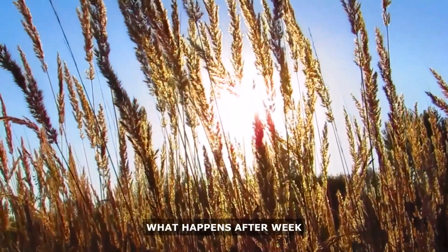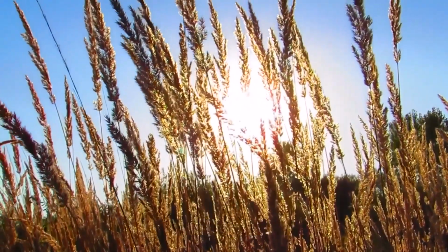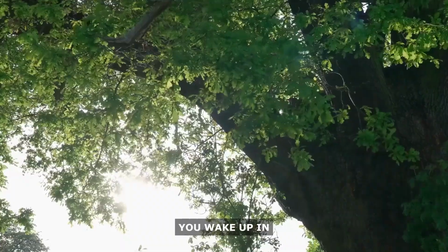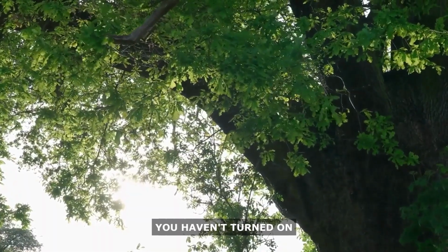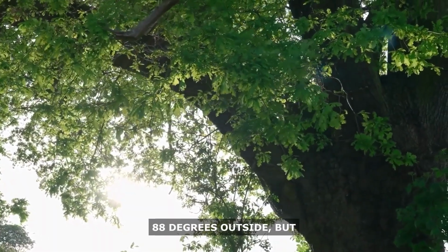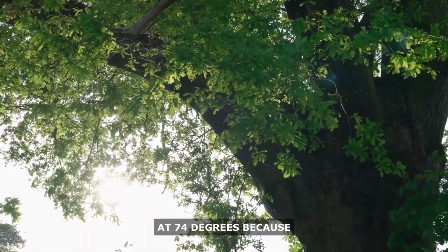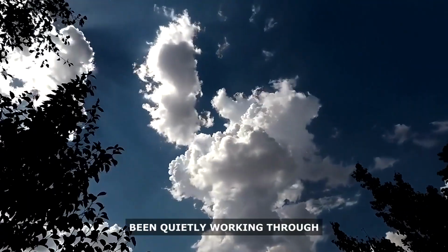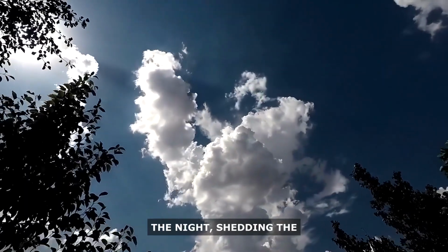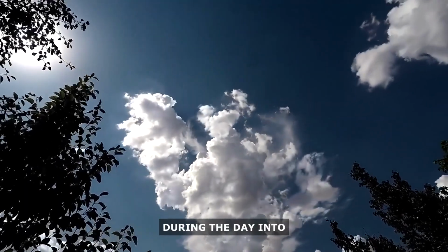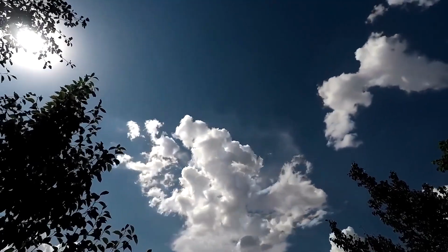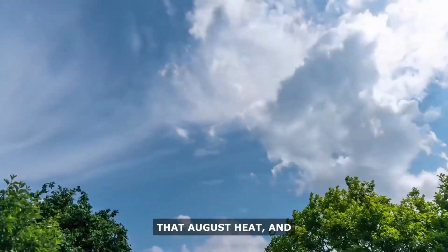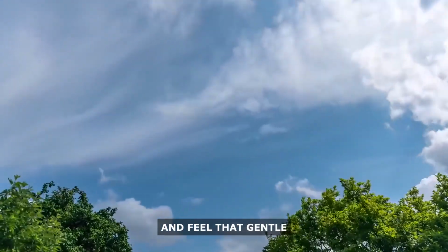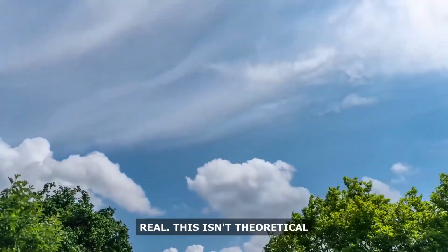But let me tell you what happens after week 2 when the system has been running steadily. You wake up in the morning and realize you haven't turned on your air conditioner. It's 88 degrees outside, but your house is sitting at 74 degrees because your ground loop has been quietly working through the night, shedding the heat your house accumulated during the day into the cool earth below. You step outside, feel that August heat, and then step back inside and feel that gentle coolness. The contrast becomes real. This isn't theoretical anymore.